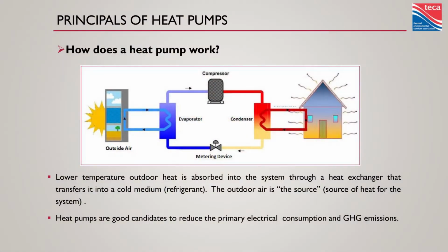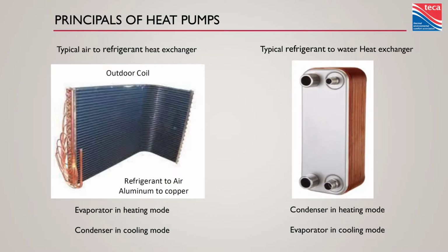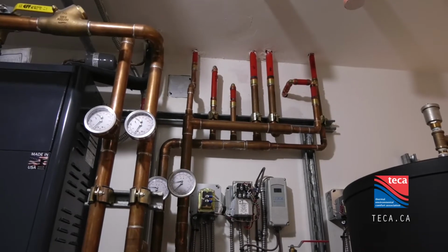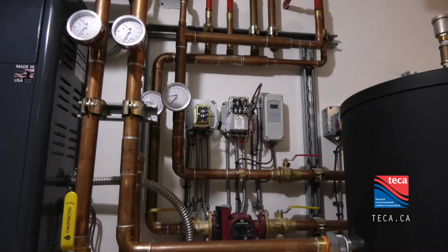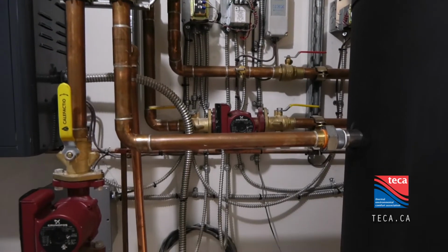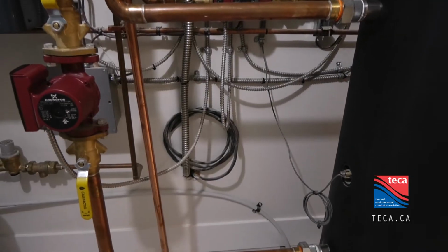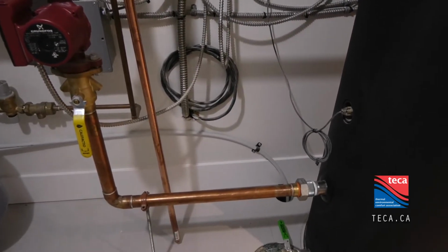So we've got, in an air-to-water heat pump, two heat exchangers: refrigerant to air, and refrigerant to water. On an air source heat pump, where air is our energy source, that's going to be sitting outside, like this large coil on the left side. It comes in all kinds of shapes and sizes, usually copper tubes with aluminum fins. And then inside, we take that refrigerant and transfer heat into water. That's usually a brazed plate heat exchanger like we've got on the right here. Things come in all kinds of shapes and sizes as well. There are coaxial heat exchangers. Can't cover them all, there's lots of stuff. But nonetheless, we're taking heat from outside air and moving it into hydronic heating inside.